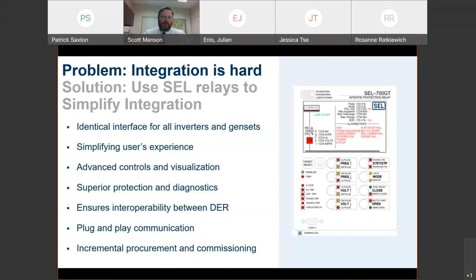So what do we do? At SEL, we put a relay on every inverter. We abstract that complexity away from the user, and we provide a simple unified interface in the relay that looks the same for every manufacturer, with the same push buttons that do the same things. We translate this unified interface, which a technician has to learn once, for any number of hundreds of different inverters or generators. So you can see the value is big. Number one value statement is simplifying the customer's experience. This is the number one reason that these relays are put on microgrids and inverters especially.